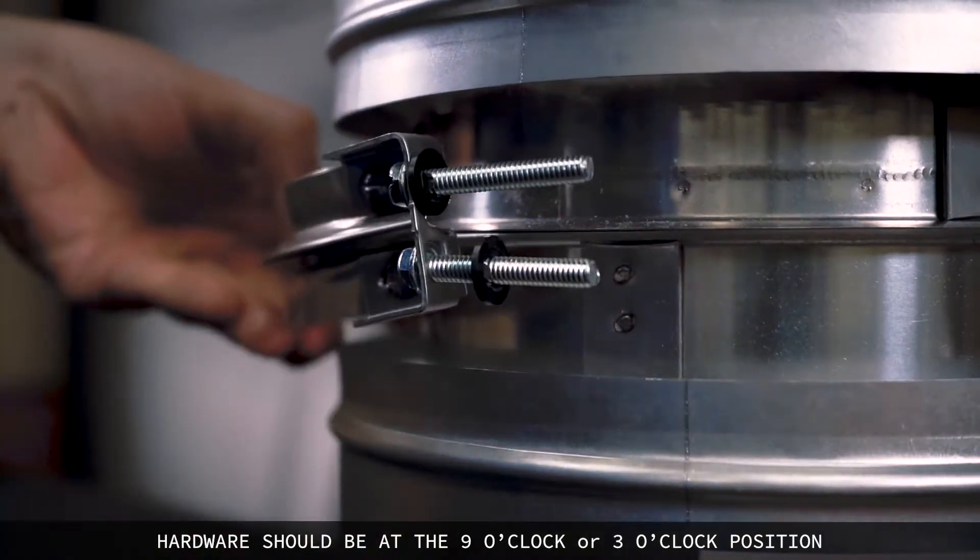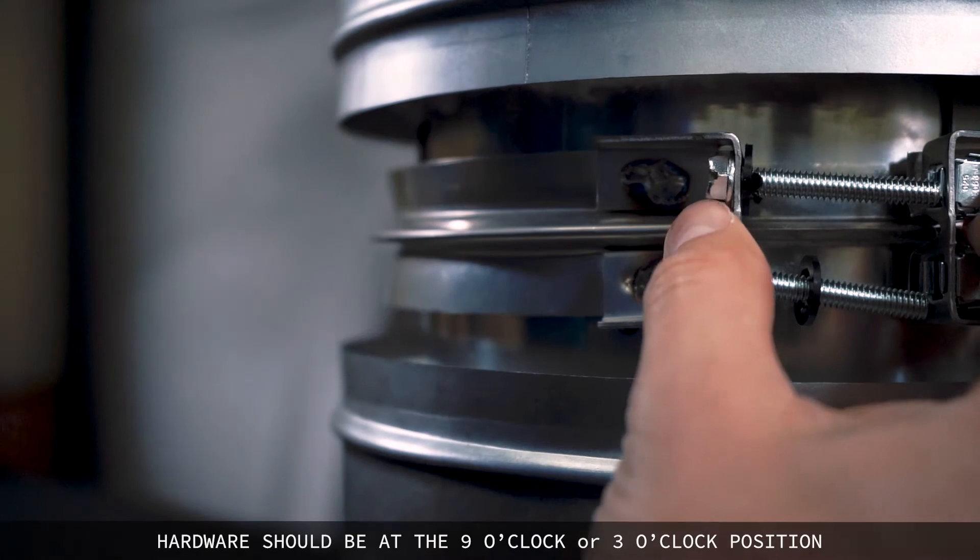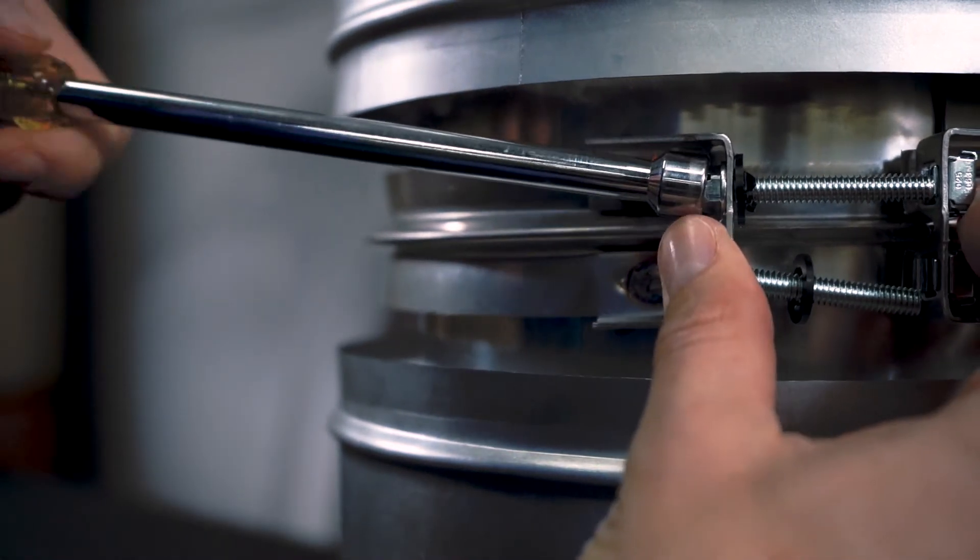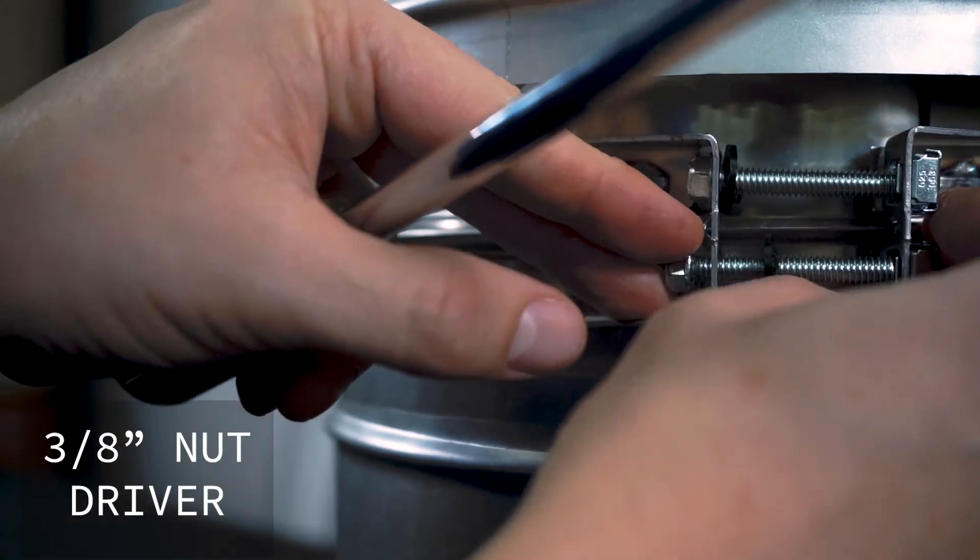For horizontal installations, do not locate the fasteners of the flange band on the bottom side of the vent pipe. To avoid cross-threading the nuts, use a 3/8 inch nut driver to start the flange bolts.